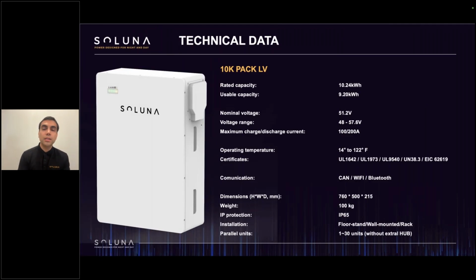This is our 10K low voltage, rated capacity 10.24 kilowatt hours. The usable capacity is 9.20 kilowatt hours. Nominal voltage 51.2 volts. The voltage range is 48 volts through 57.6 volts. Maximum charge at 100 amps, and the maximum discharge current is 200 amps. This is also 1C rated, which allows you to charge and discharge within an hour. The operating temperature is also -10 Celsius to 50 Celsius. And the certificate is UL 9540A, with communication CAN and Wi-Fi.